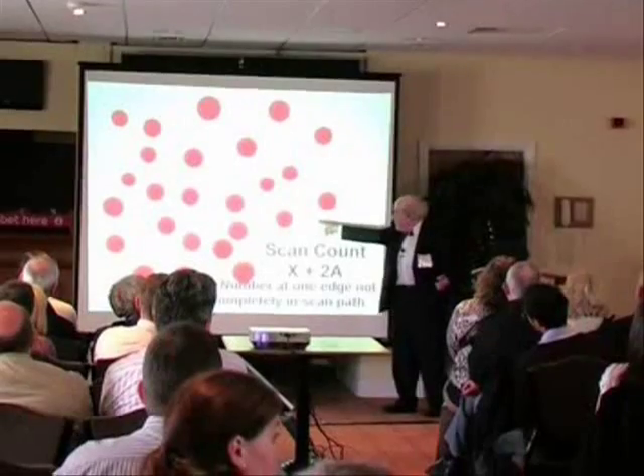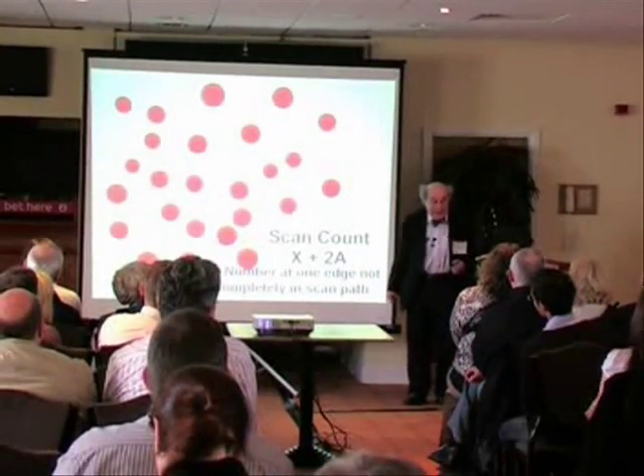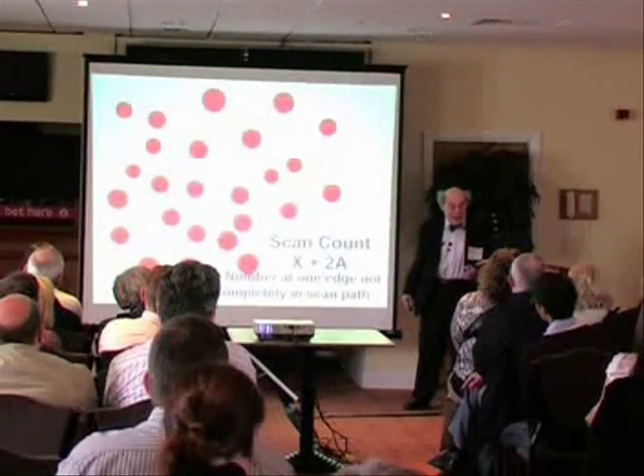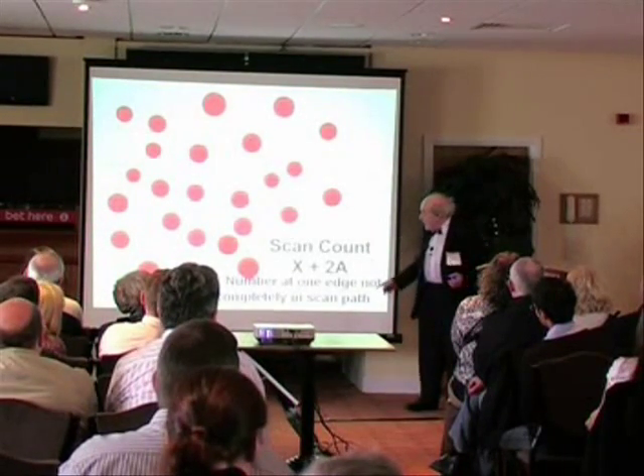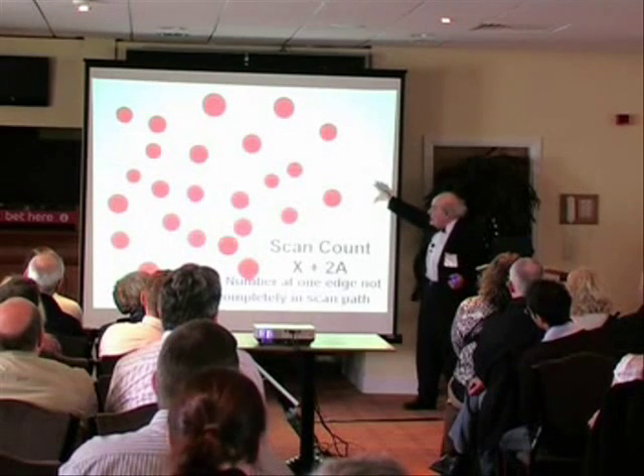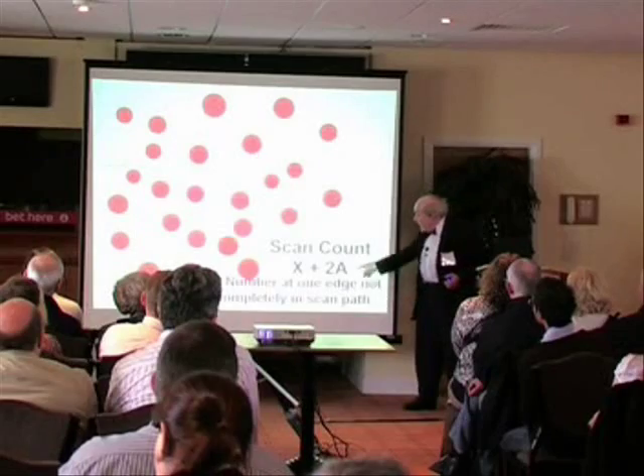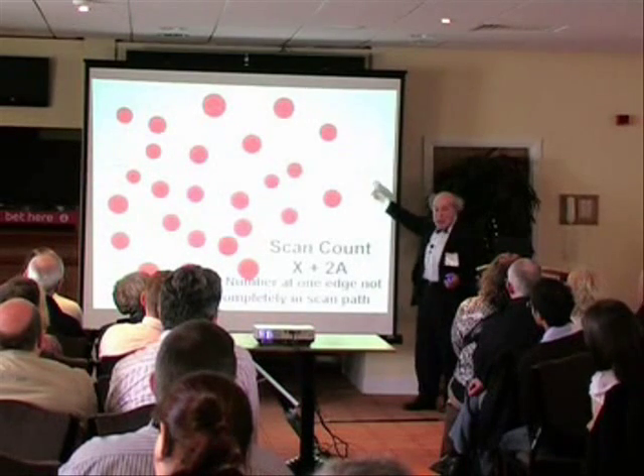Imagine you have that little window which you see there, traveling across a plane full of blood cells. You obviously count all of those which are inside the track, but you also count some of them which are either wholly in it or only poking a little bit into it, depending on how sensitive the system is. So you get an error and you don't actually know what that error is. You get the right number — those which are properly within it — and you get an error which is due to the two edges.